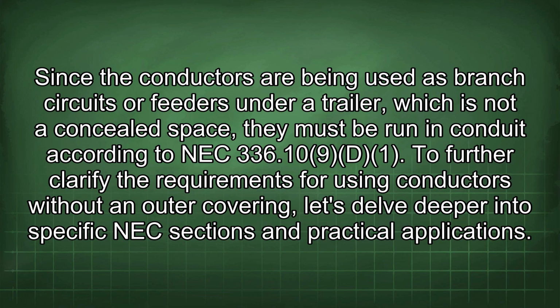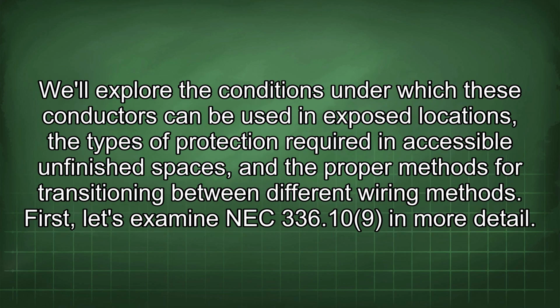To further clarify the requirements for using conductors without an outer covering, let's delve deeper into specific NEC sections and practical applications. We'll explore the conditions under which these conductors can be used in exposed locations, the types of protection required in accessible unfinished spaces, and the proper methods for transitioning between different wiring methods. First, let's examine NEC 336.10(9) in more detail.